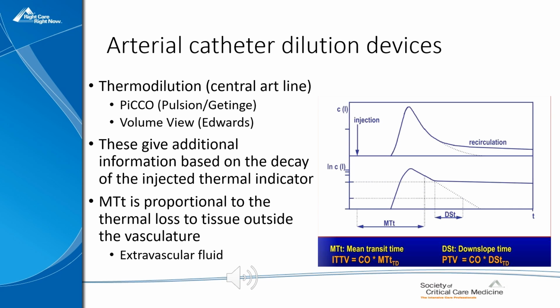Some of the additional information that comes off of the calibrated central arterial catheters that use cold thermodilution through a central arterial line, like the PiCCO device or the VolumeView device, is they give lots of additional information based on the decay characteristics of the curve, the decay curve characteristics of the injected thermal indicator. For example, the derivative of that slope is a measure of the thermal loss of fluid to the tissue outside the vasculature, which is used to estimate the amount of extravascular fluid, giving you a measure of extravascular lung water.